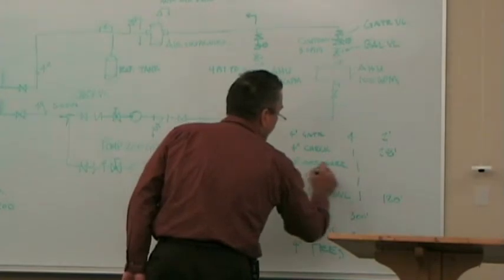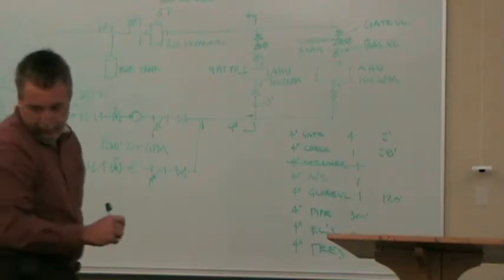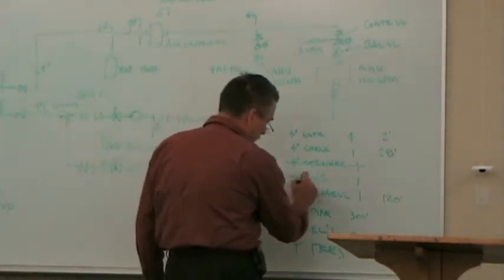Okay, strainer we moved out. And an air separator, not very much, we'll look at it anyway. I'll get on in a minute. 4-inch. It's the actual pressure. It's about 8 feet. So I know what the actual pressure drop of that is at my known flow.